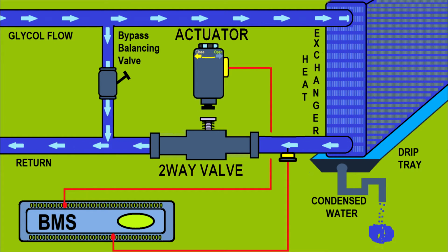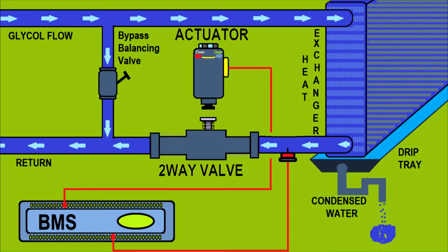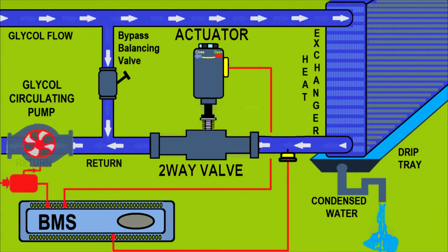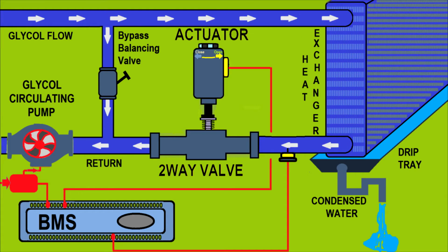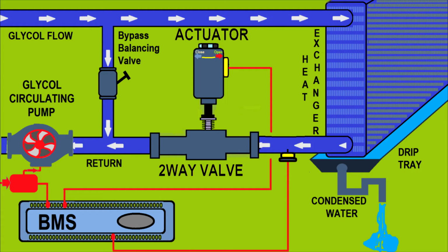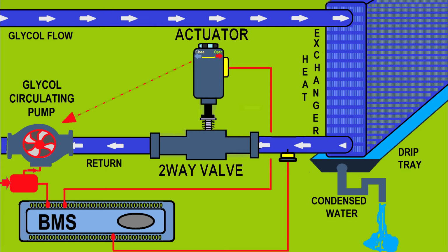So also, if you look at the actuator, this is in fault condition. The actuator wants to close the system because the premises might be too cold, but the shaft of the two-way valve is broken, and no matter how much you manipulate the actuator, the two-way valve is seized because it might be corroded or damaged. In this situation, you'll see we run a pump, and to control the capacity of the cooling we use the actuator, because this is probably just a branch.